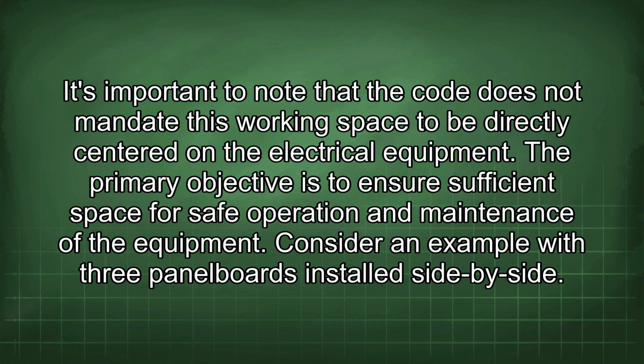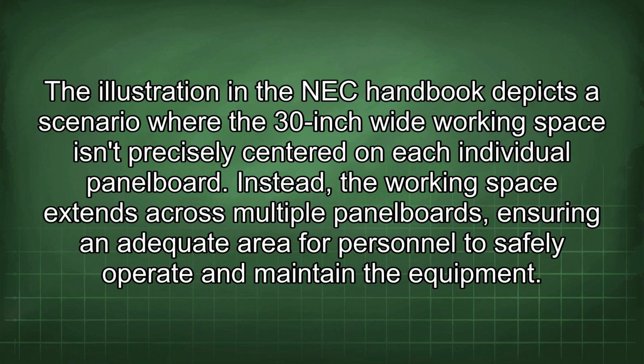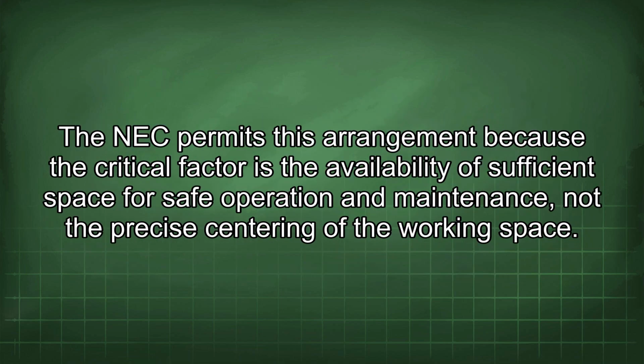Consider an example with 3 panel boards installed side by side. The illustration in the NEC handbook depicts a scenario where the 30-inch wide working space isn't precisely centered on each individual panel board. Instead, the working space extends across multiple panel boards, ensuring an adequate area for personnel to safely operate and maintain the equipment. The NEC permits this arrangement because the critical factor is the availability of sufficient space for safe operation and maintenance, not the precise centering of the working space.